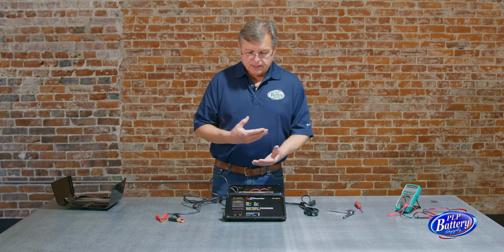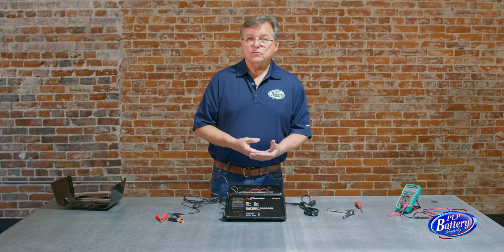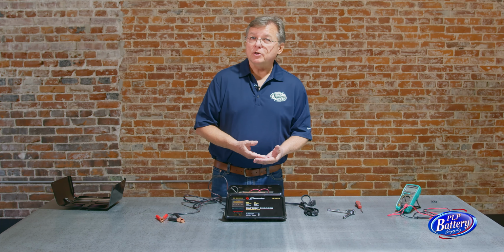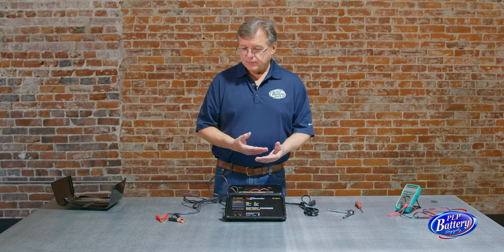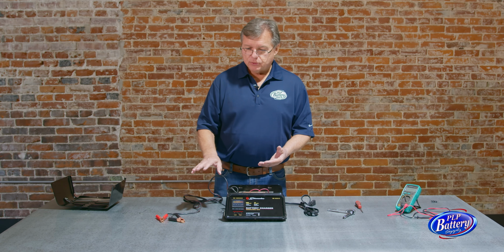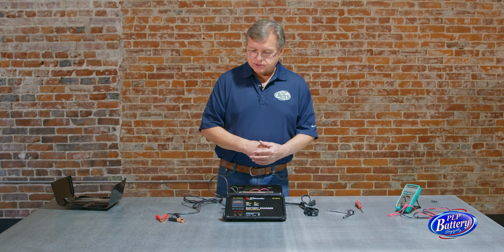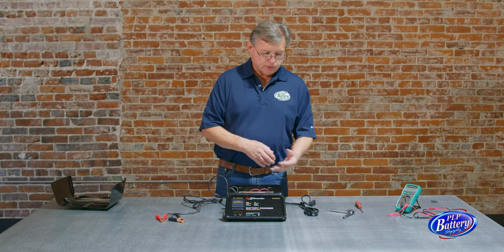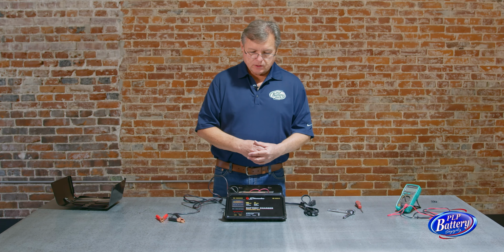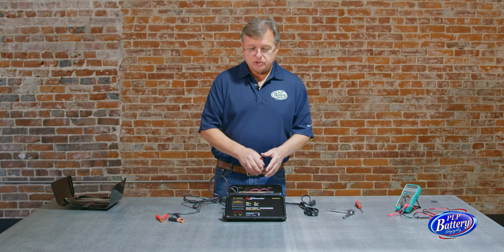If you've got a charger that's not working, the first thing you need to determine is if it has AC input that's making it to the transformer. In other words, can you hear the transformer hum? Have you tested to see if there's any output at all? Is it just low output, or no output at all?